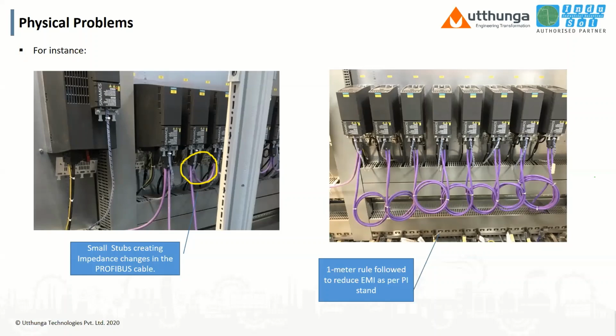But what's actually happening here? Due to these small stubs, the impedance changes. The impedance of Profibus cable is 150 ohms. If impedance changes, the entire communication changes, right? That's what happens in the network. Then what we recommended to the plant is the 1 meter rule. With the 1 meter rule, the drives have a specific distance in between and the interference got reduced. You can see here clearly that with 1 meter cable, we have connected the drives.